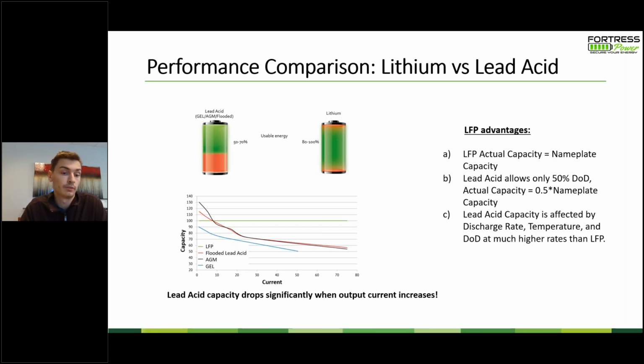Now if you look at the other three lines, we have flooded lead acid, AGM, and gel battery. A common question is: flooded lead acid may have a high capacity, but as soon as you start pushing current out to loads, that capacity drops. So you're getting less bang for your buck, less power out of that lead acid battery than a lithium one, because of the chemical makeup of the flooded lead acid, AGM, or gel.